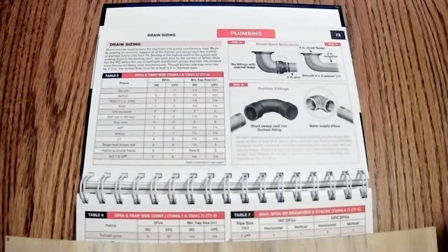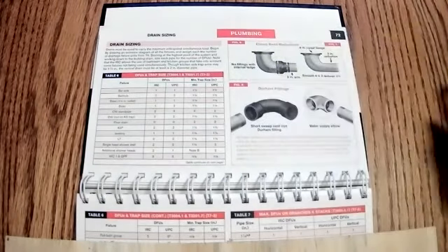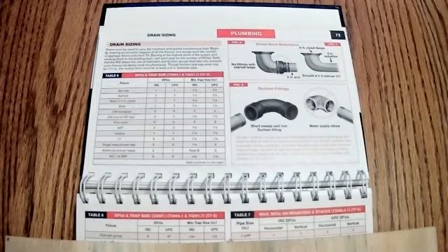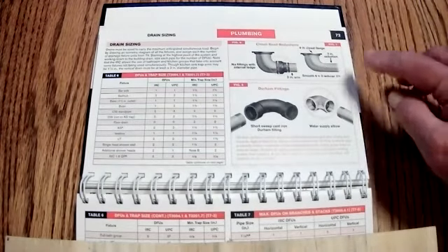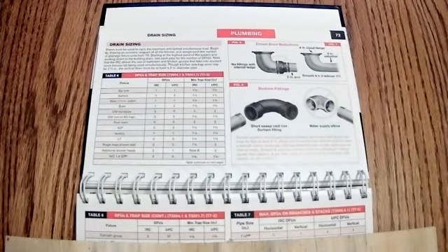So that being said, now let's look at some of these fittings on the next page. This is coming off the closet, which has a 4-inch flange on it, going down to a 3-inch pipe. That is not acceptable, because you're reducing it down. The one to the right shows that you can reduce it down with the proper fitting. That's a smooth 4 to 3-inch reducer, and that's going to be okay. I talked about that at the school. We had it in a gym situation, and that's what we've done now. So that being said, we're moving on.